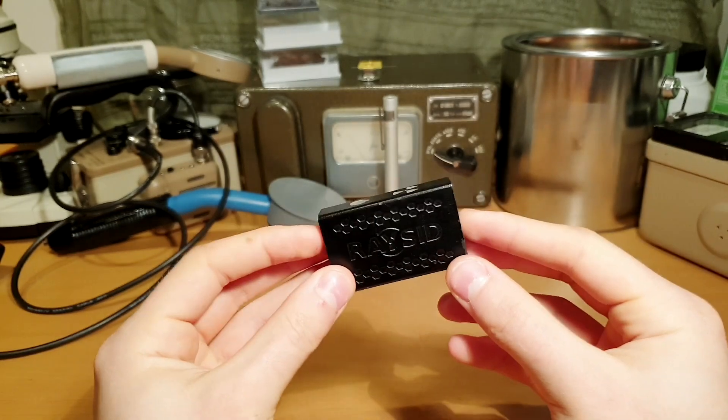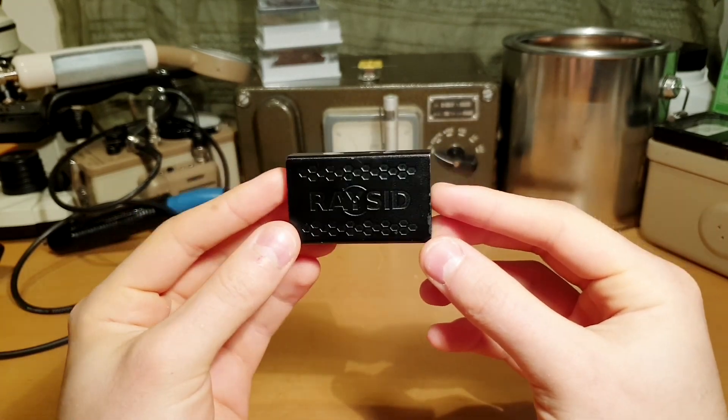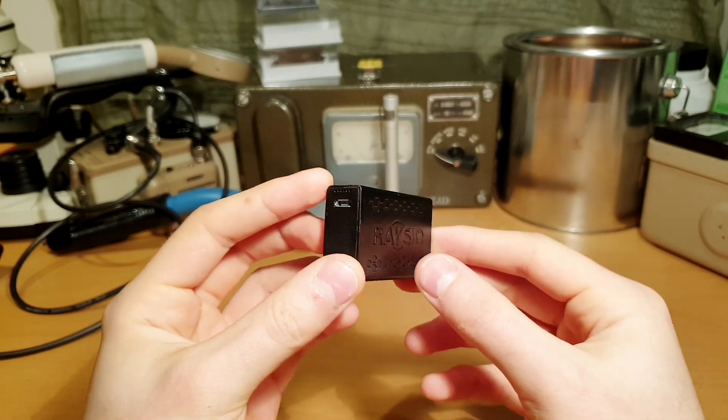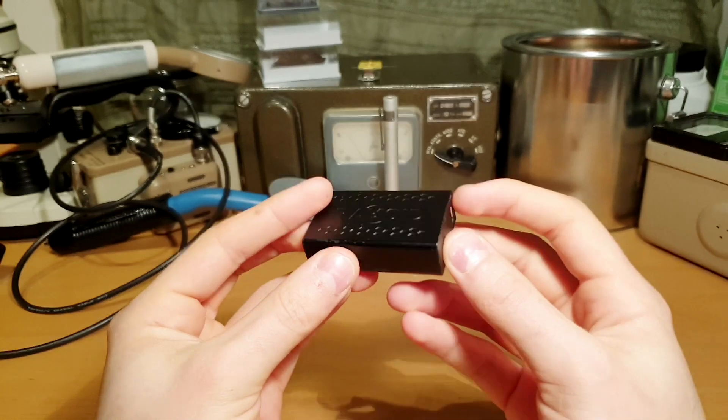In terms of size, RaySID is comparable to a lighter and weighs only 65 grams. Inside, there's a rechargeable battery that lasts for over 10 days on a single charge. The heart of this device is a 5 cubic centimeter thallium-activated cesium iodide scintillation crystal.